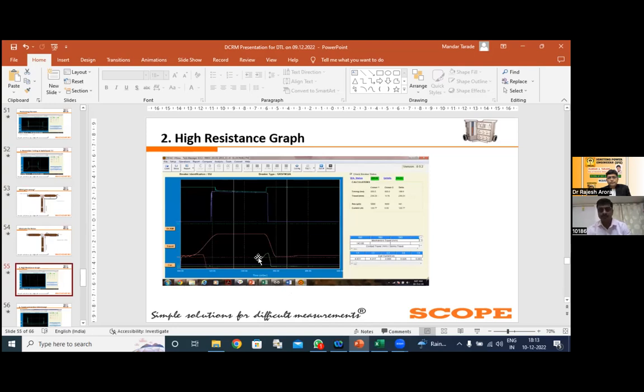Now here, the high resistance graph. The high resistance graph is coming because there may be several reasons. First thing is that your contact is not healthy. Second thing is that your cable, which is used for injection of the current, or which is used for taking the voltage drop, is not healthy. Your channels are not working properly, or your signal conditioning circuit, which is available in the analyzer, is not working properly. Or the fifth important thing is that the person making the connection on the CB, instead of making the connection on the flange, has made the connection on the loop, or on the jumper, or on the conductor. Or in case of 400 kV, maybe he has connected the cable to the PIR contacts. That may be one of the reasons.